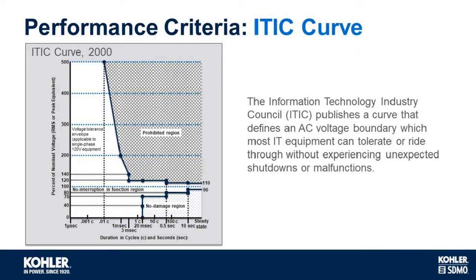Another performance criterion that's important in data centre applications: the ITIC publish a curve that defines the AC boundary which most equipment can tolerate or ride through without experiencing unexpected shutdowns or malfunctions. Therefore, any power delivered to the IT stack needs to stay within these boundaries.